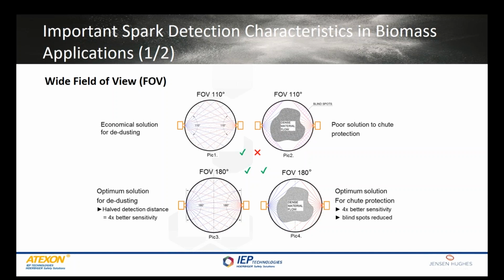Biomass processes set new requirements for spark detection. Conventional spark detectors, which are especially designed for low-dense material flow, have a limited viewing angle or field of view. Picture 1 describes that a detector having a 110-degree viewing angle works without any problems with dust extraction pipes, because the opposite detector covers blind spots of the other detector. Picture 2 shows what will happen if the same detector is used for biomass applications having dense material flow. The opposite detector can no longer cover blind spots of the other detector, and the risk of unrecognized ignition sources is significantly increased.